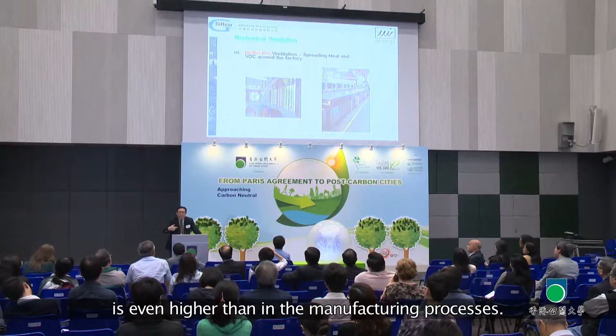In most industries, they install mechanical ventilation. In most factory owners' minds, ventilation fans just use small power, so they just let it run. But in reality, in some factories, some workshops, I found that the energy consumed in the ventilation system is even higher than in the manufacturing processes. That's the fact. Therefore, after refining the design of the ventilation, a lot of energy consumption has been saved.